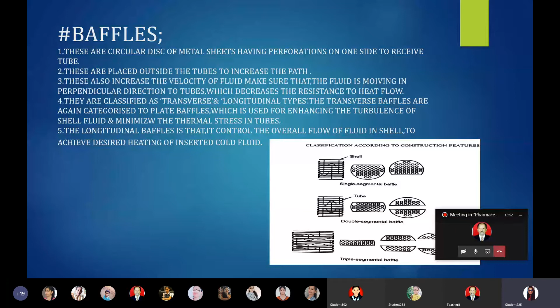liquid to liquid heat interchangers, where the construction aspects tell us it consists of tube sheets, spacer rods or spacer tubes, guide rods, and various inlets and outlets. The second point says the tube sheets are attached to the guide rods. Baffles are attached to the perforation side where the tube is getting inserted. The whole assembly is covered by the shell casing. There are two distribution chambers, where one is used for the inlet of cool fluid while the subsequent one is used for the outlet of hot fluid or heated fluid.